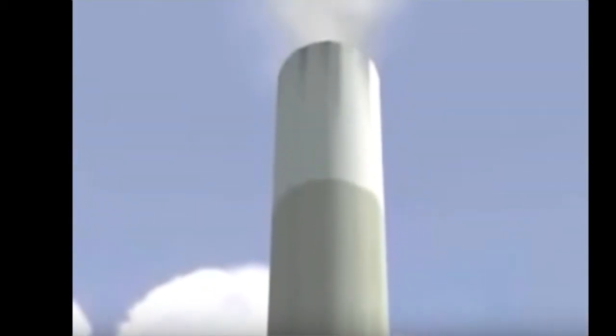Scrubbers. This particular plant is equipped with air quality control systems to remove sulfur dioxide and particles called fly ash. Fly ash is removed by a mechanical process, and sulfur dioxide is removed with a chemical reaction using lime. These processes take place in large ductwork scrubber trains located between a unit's boiler and its chimney. Boiler gas passes through scrubbing vessels and is sprayed with slurry, a mixture of water and lime. The sulfur dioxide particles and other pollutants are absorbed by the slurry and fall to the bottom of the vessels. A fan releases the clean gases through the chimney.